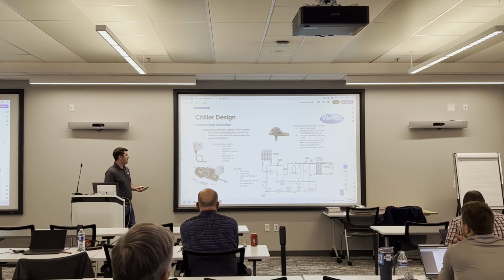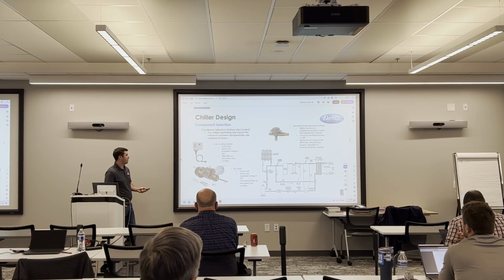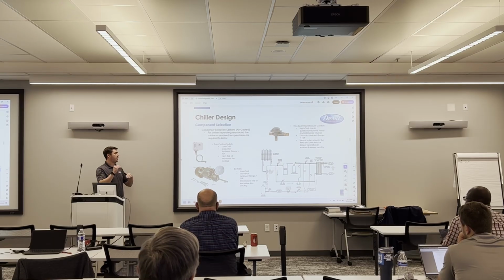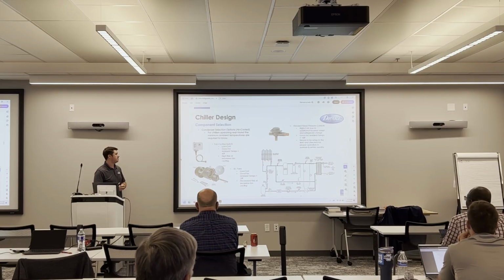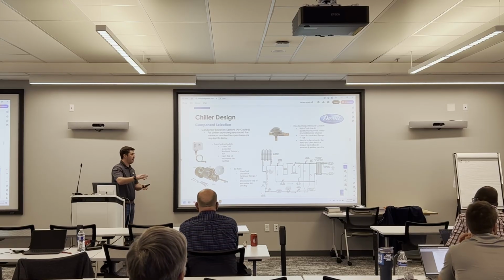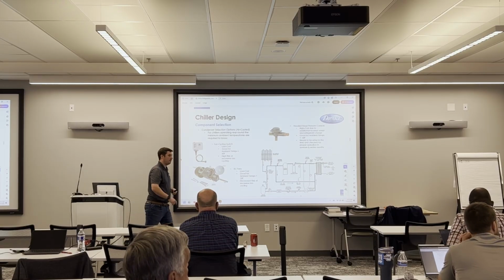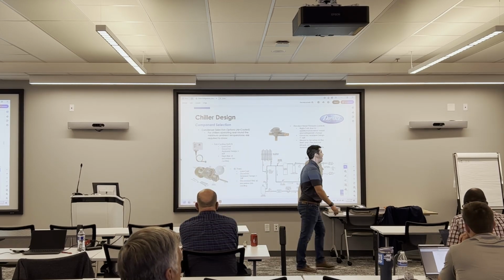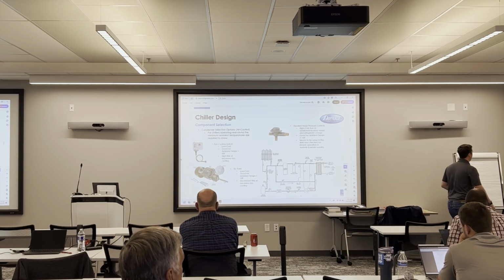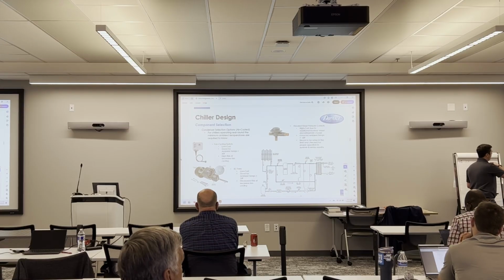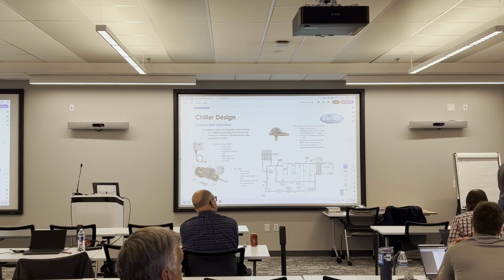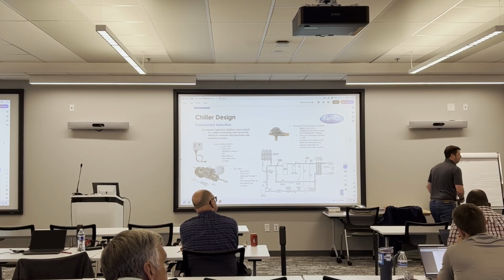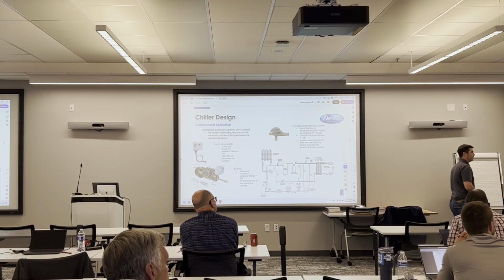Some other options for the fans, we can do an electronically controlled fan, call that an EC fan. Again, low cost. That's good for ambient temperatures as low as 10 degrees. Essentially what we're doing is modulating the fan speed, changing your RPMs, changing your CFMs, delivering a slower flow rate of air across the coil. Good. What horsepower limitations are those EC fans? We use 1 horsepower on our standard units, but you don't go much bigger than that, do you? The example I had on the previous slide, they're about 3 horsepower. Excellent. I'm sure they make all different kinds, but they're pretty much limited to smaller motors.